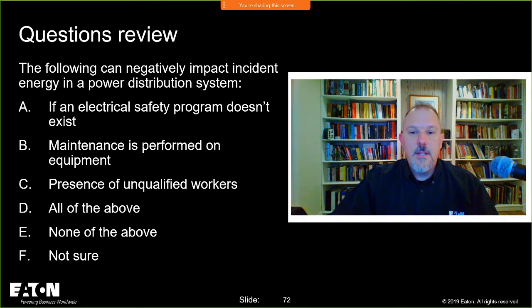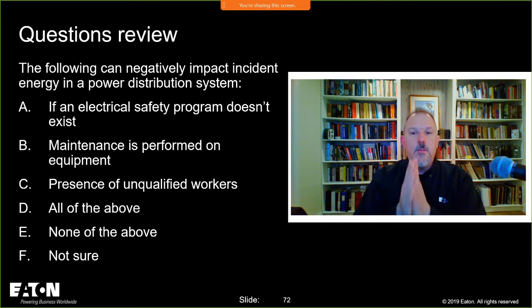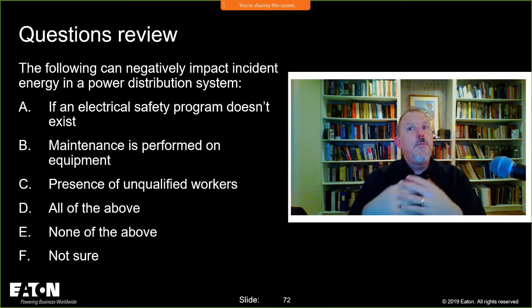Okay, so there's the sign in. I see you guys are communicating. What is your opinion about arcing fault sustainability for 240 volt single phase panel boards? All right, so here's what we're doing on the single phase. The new IEEE 1584 did some more testing, and they removed that small transformer. Remember, there was a small transformer size below which you didn't have to do arc flash analysis. In the case of 240, 208 volts, and the single phase stuff, we haven't established the floor.